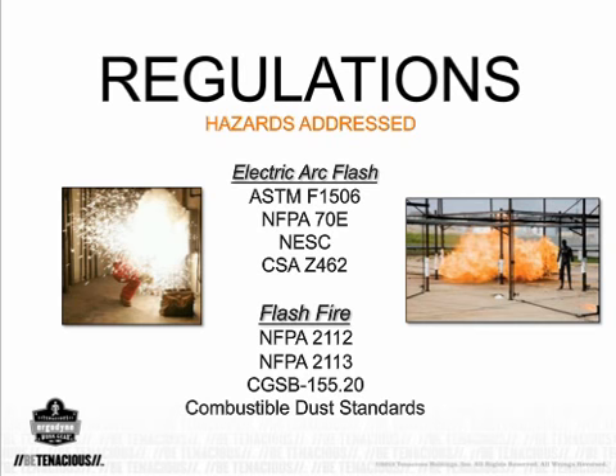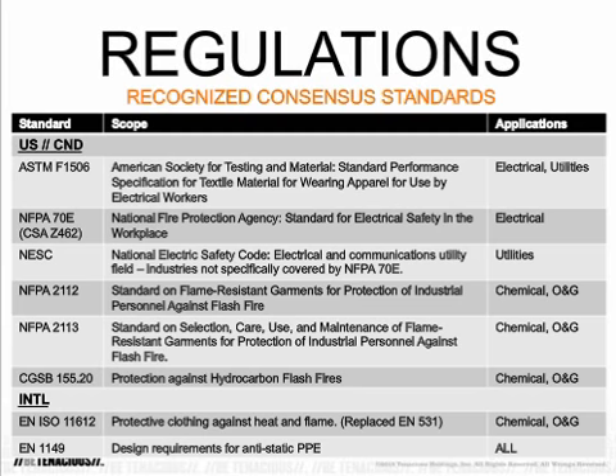After having had a risk assessment, the employer will have a clear understanding of what hazard exposures their employees face. With that said, the above are the standards that employers should pay closest attention to. So let's take a look at each standard in a little more detail. ASTM F1506. First, ASTM stands for American Society for Testing and Materials. This is the standard performance specification for textile material for wearing apparel used by electrical workers. What that means is that the fabric used to make the garment has been tested and received an arc rating or an ATPV value, which is an arc thermal performance value, per the ASTM F1959 standard.